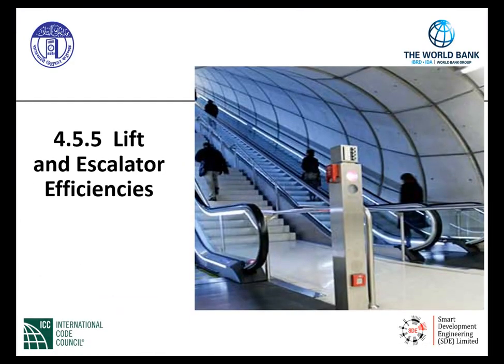4.5.5 talks about lifts and escalator efficiencies. So there's ways to save energy in buildings that have elevators and escalators. For escalators, we see in section 4.5.5.1 that in buildings of all occupancies, if there's an escalator, it has to be fitted with controls to reduce the speed or stop it when no traffic is detected. And so there's a couple ways to do that. There's some energy features, and it gives you a couple.